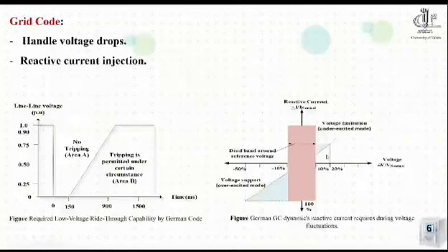We see it is required that the renewable energy source support the grid voltage by supplying more reactive current when the voltage drops. Actually, when the voltage drops by more than 50%, the converter must inject 100% reactive current, and of course this depends on the converter design.